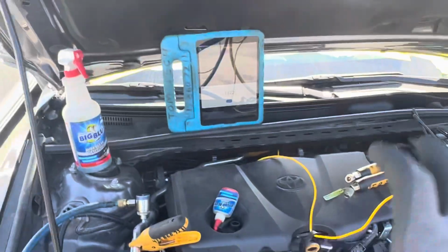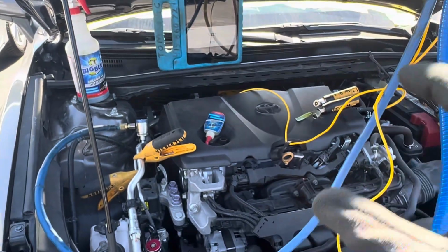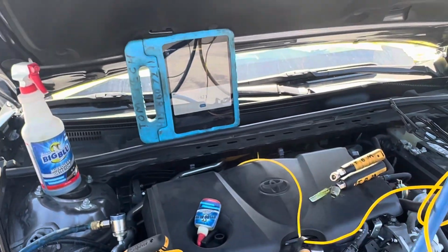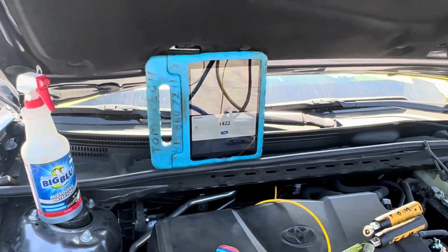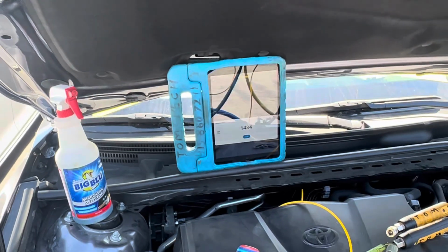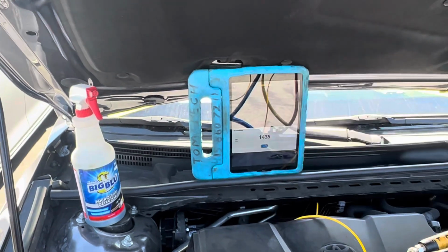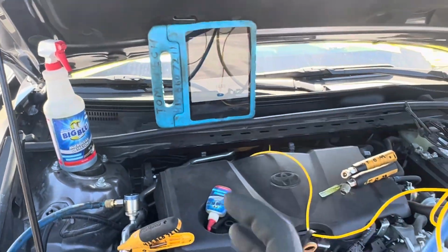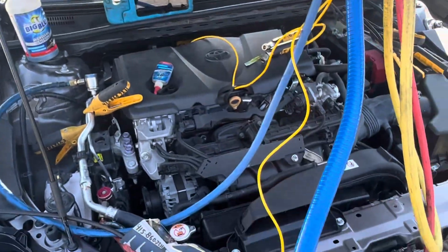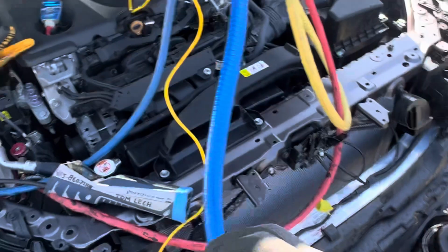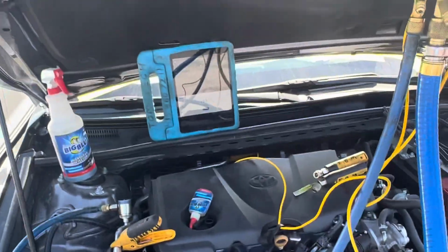And that's under these conditions. There are other cars that are so moisture contaminated I could be on here an entire hour and it'll still decay up there at 1,500, 2,000, 3,000 microns because the system is just overly saturated with moisture. A vacuum pump doesn't take it all out within an hour.